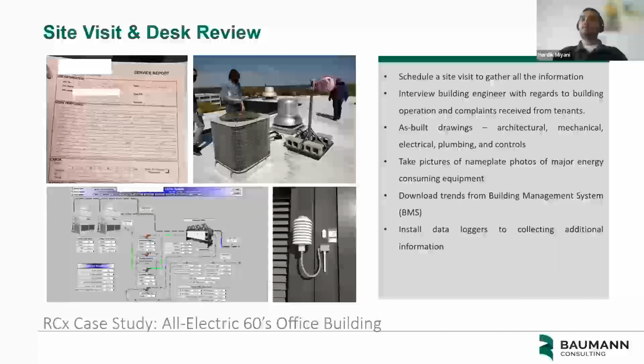This was very helpful for this particular project because we started this project in early summer, and we were looking for energy saving opportunities during winter as well. So with the trend data capability that was available in the BAS for this building, we were able to see the building performance during fall, spring, and winter months as well. So it helped us not only to focus on the energy saving opportunities for the summer months, but also throughout the year while it was getting implemented and verified at a later stage.